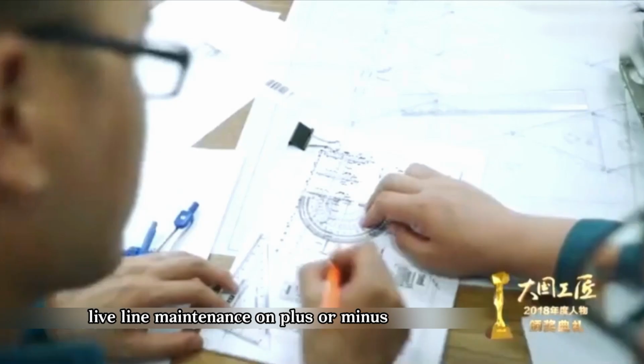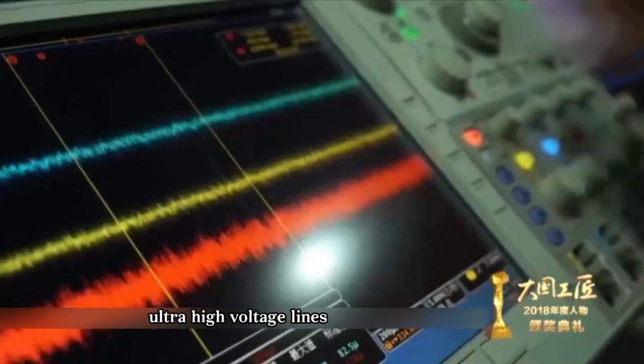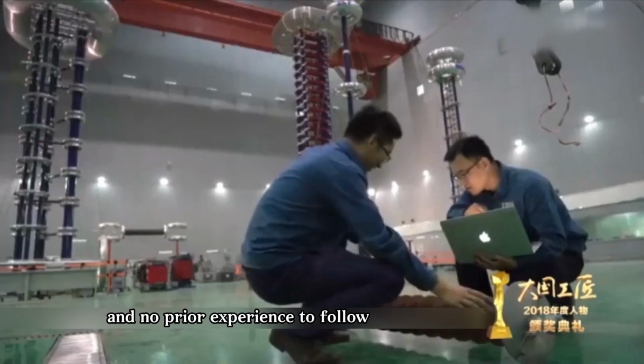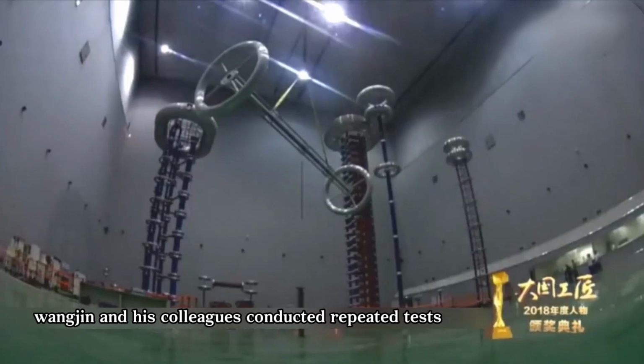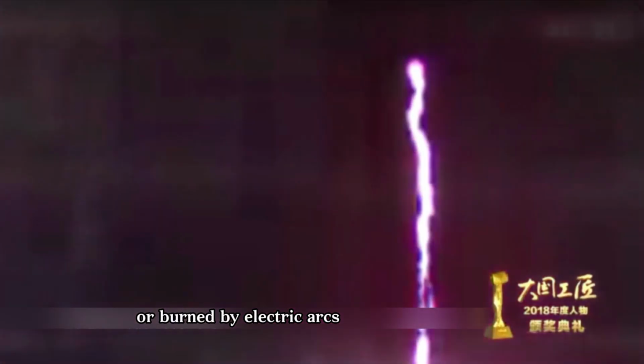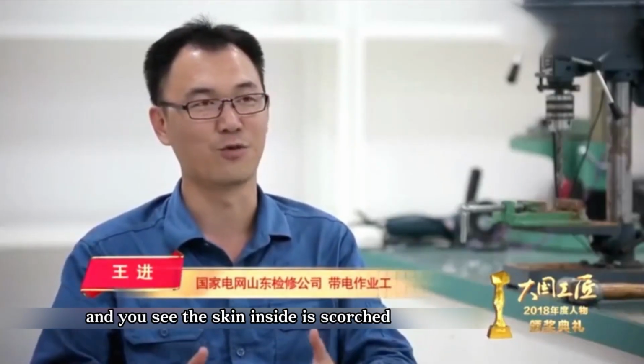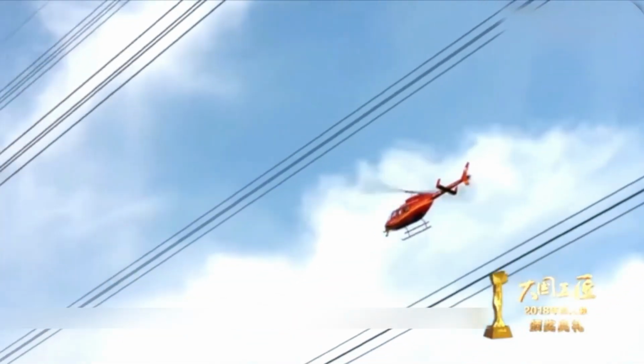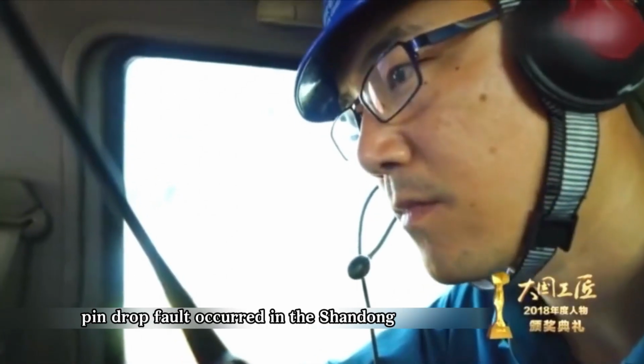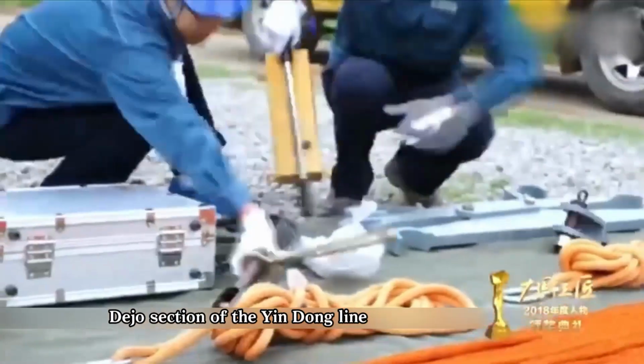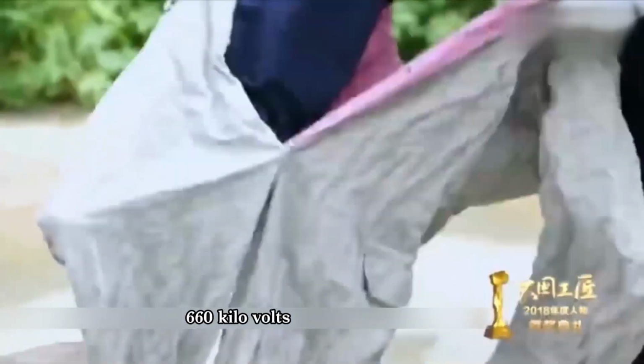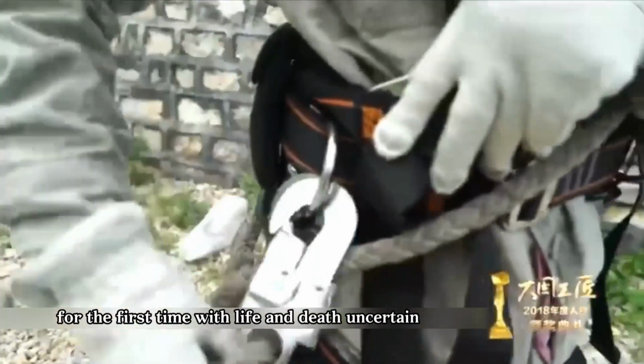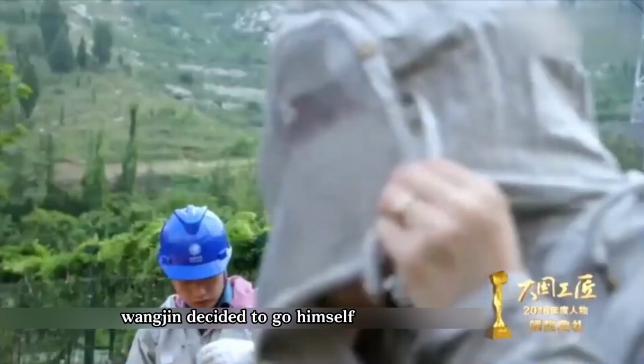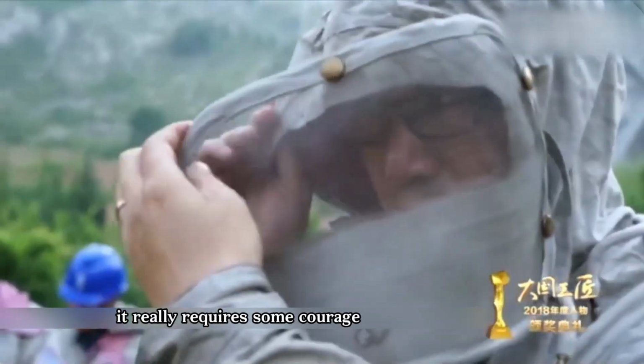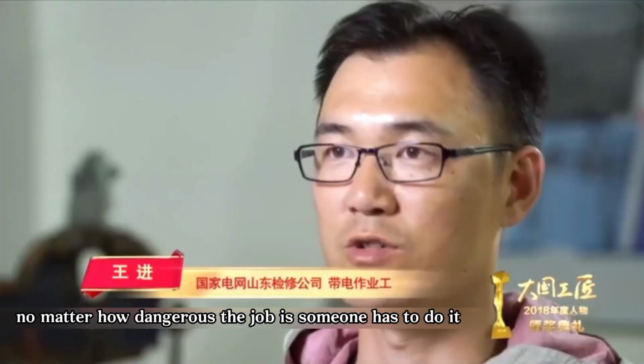Live line maintenance on plus or minus 660 kilovolts ultra-high voltage lines had no precedent in the world and no prior experience to follow. For this reason, Wang Jin and his colleagues conducted repeated tests, watching helplessly as dummies in shielding clothing were struck or burned by electric arcs. If it's taken down and you see the skin inside is scorched, this distance is not acceptable. On October 17, 2011, a pin drop fault occurred in the Shandong-Dezhou section of the Yindong line. Facing the plus or minus 660 kilovolts ultra-high voltage DC strong electric field for the first time, with life and death uncertain, Wang Jin decided to go himself. It really requires some courage. No matter how dangerous the job is, someone has to do it.